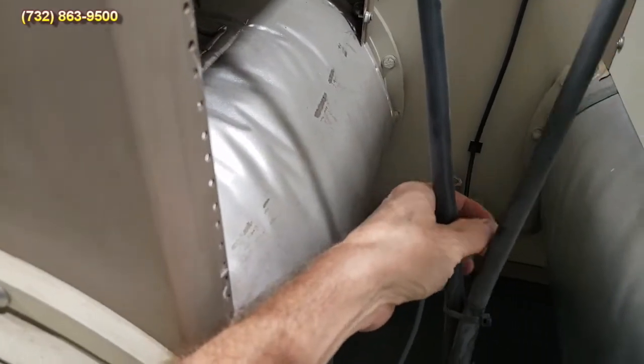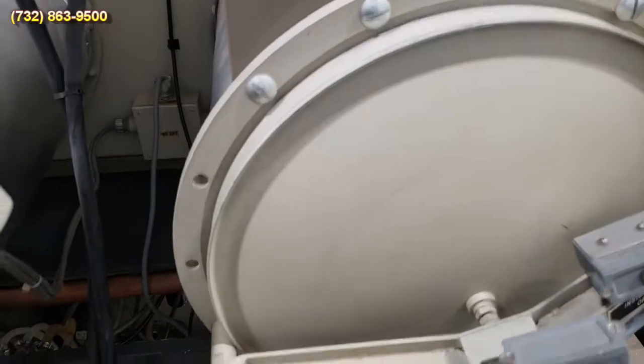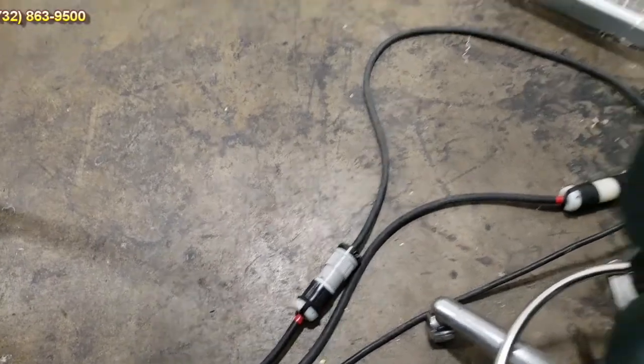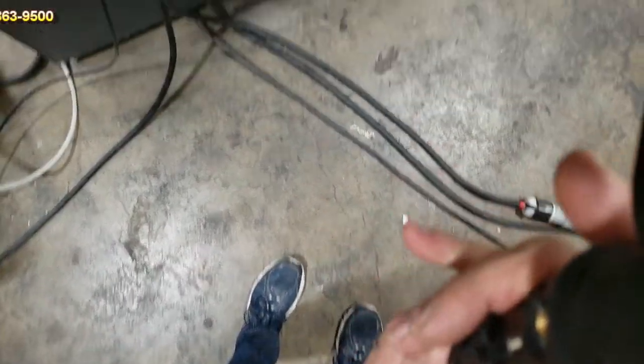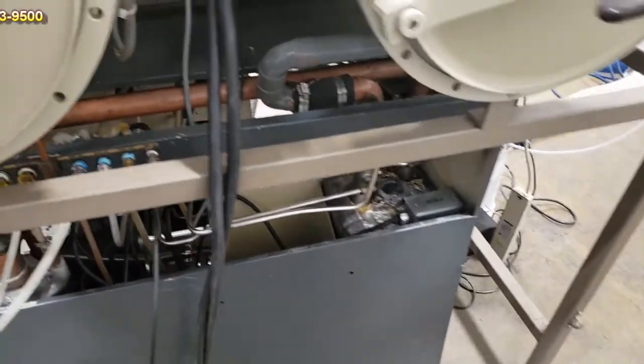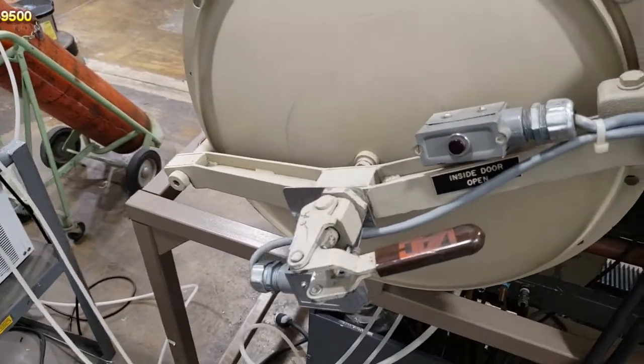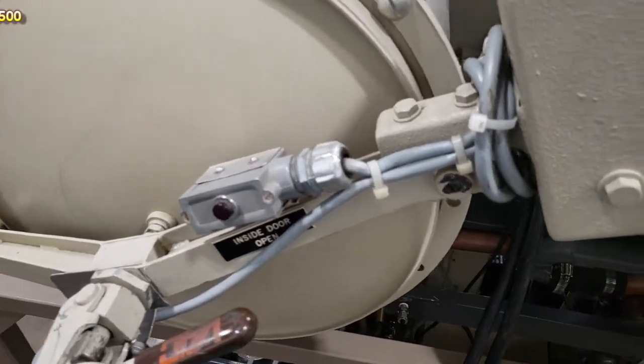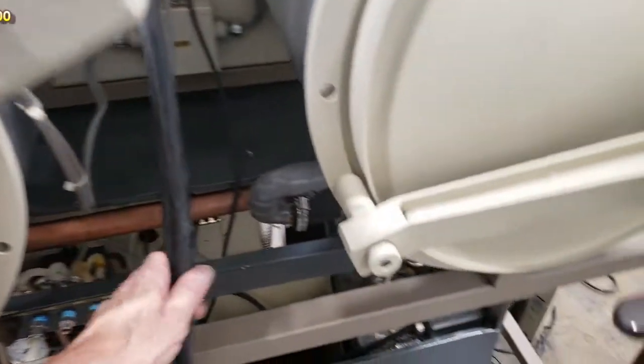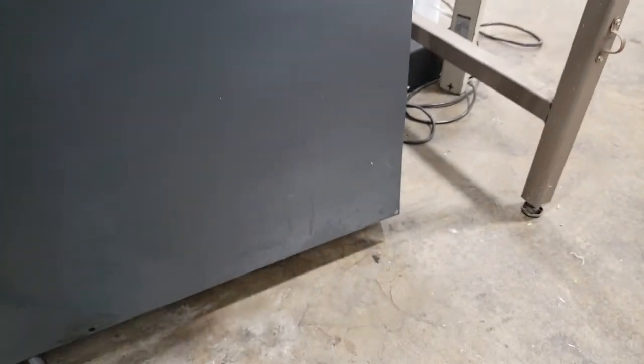I just want to take this back cover off and point out a few things. While we're here, there's a line for each one. This is a 208 single phase, 20 amp plug for each one of your antechambers. And I have it connected down here, and I bring that up to our wall. Alright, so each one of the antechambers requires a 208, 20 amp circuit. It has its own individual plug. The system alone also requires 208 and has its own plug.